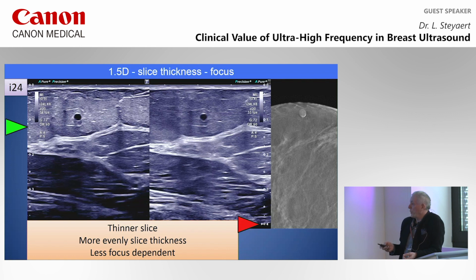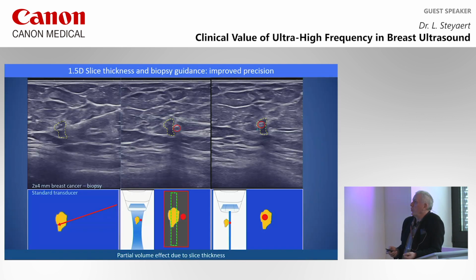And this is what we have now with the Matrix 1.5D. It's a 24 megahertz probe here. We use it at 20 megahertz. You have a small cyst and the focus is okay, but if the focus is very low, you still see the lesion very well. And that's important. You have an even slice thickness, which is less focus dependent than in a normal probe.